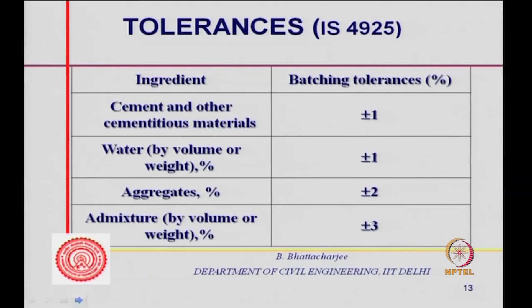And this is meant for 30% of the minimum weight, that is, 30% of the scale capacity divided by the weight tolerances given in the previous table. For example, let us say I have a maximum capacity of about 1000 kg for my weighing system. So, the tolerance specified in the previous table will be applicable to 0.3 into 1000, which means 300 kg, divided by 1%, is the weighing tolerance. So, this should be applicable to 300 kg of the cement, minimum cement.